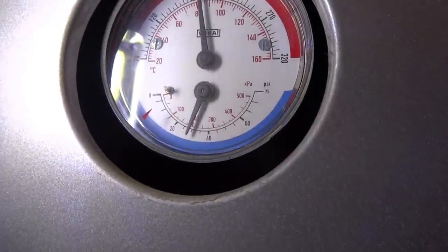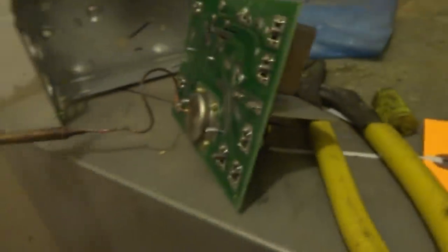And it goes to the circulator. Which valve looks a little high. Goes to the burner. I'm going to pop this off because it smells burnt. Front right there. Just four little tabs that you can bend out. Comes right out. You smell it? It's cooked.